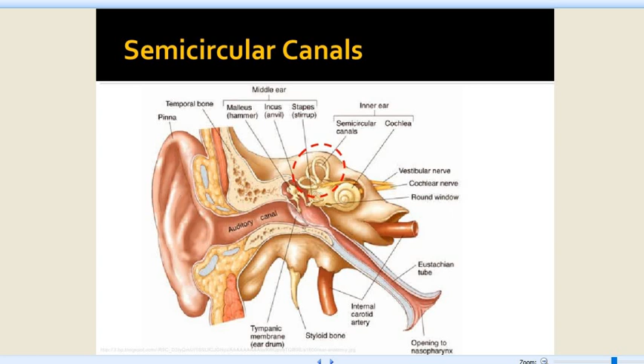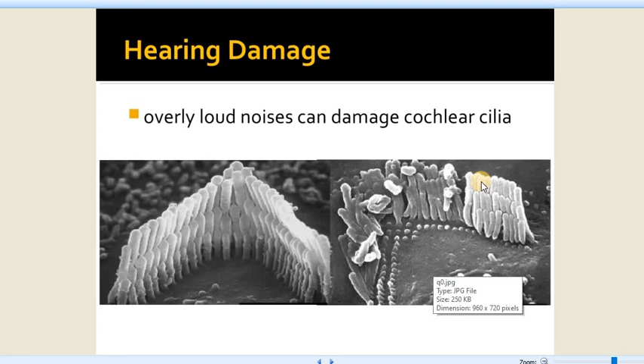The major applied physiology of the ear is related with the hearing damage, sometimes due to overly loud noises which damage the cochlear cilia. This damage can be detected in clinics by the instrument called audiometer. Audiometry is the technique which is used to determine the nature and severity of auditory defect. During the test by audiometer, the subject's ability to hear sounds with 8 to 10 different frequencies is observed, and the hearing loss is determined for each frequency by using these values. The audiogram is plotted.